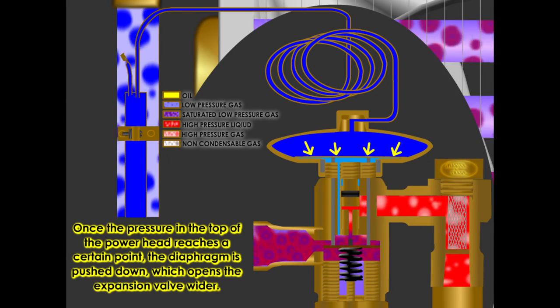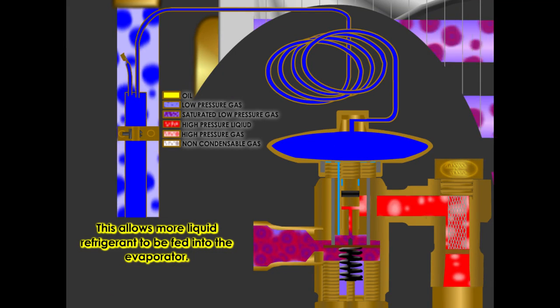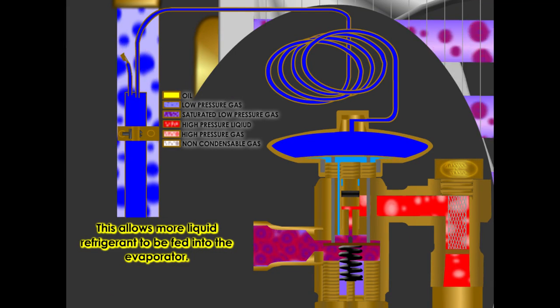Once the pressure in the top of the power head reaches a certain point, the diaphragm is pushed down, which opens the expansion valve wider. This allows more liquid refrigerant to be fed into the evaporator.